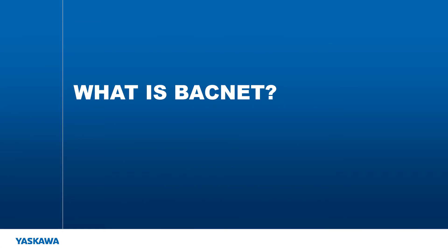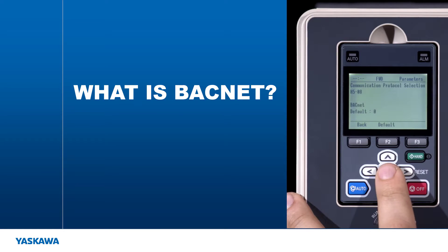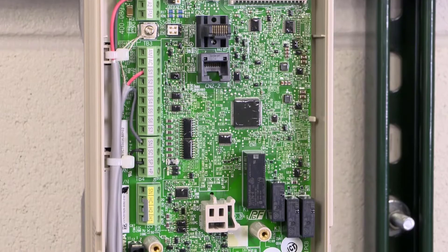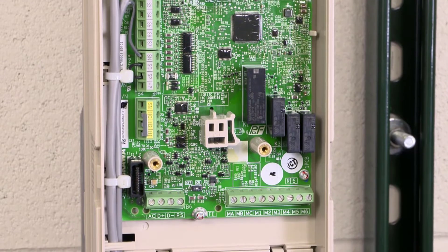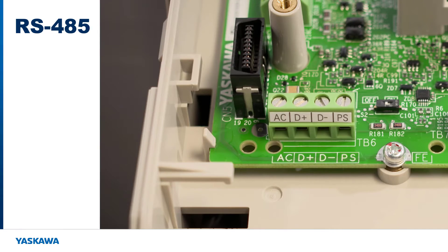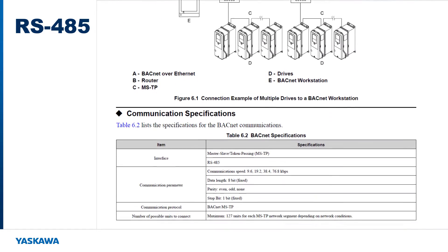Let's begin by explaining what BACnet is. BACnet stands for Building Automation and Control Network. This allows users to connect up to 127 HV600 masters and even more slave devices on a single BACnet MSTP network. This master-slave token passing protocol utilizes RS-485 technology to create one of the most widely utilized communication protocols found in commercial building automation environments.